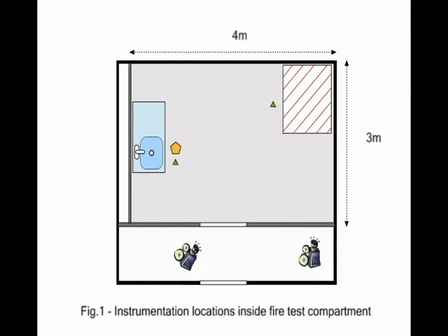For these tests we created a kitchen of 4x3 metres. The test simulates a worst case incident where the fire is around 4 metres from the Automist system and the door is left wide open. Fire and smoke sensors were placed on the ceiling close to the sink, and thermocouples measured the waist level and ceiling level temperature at two locations.